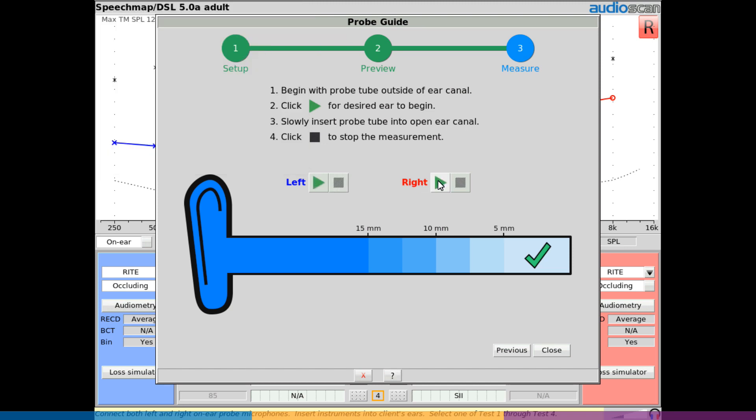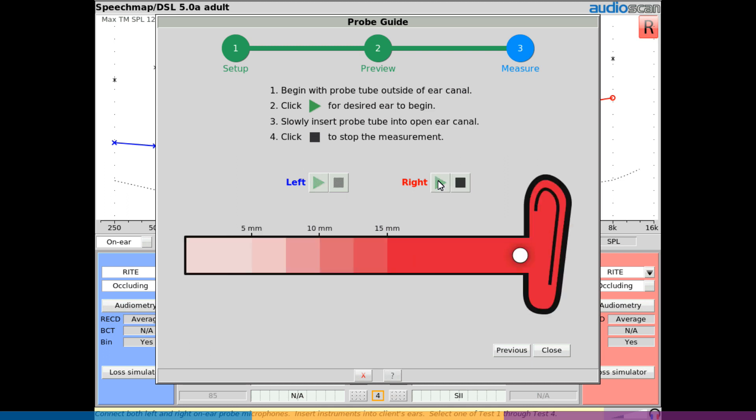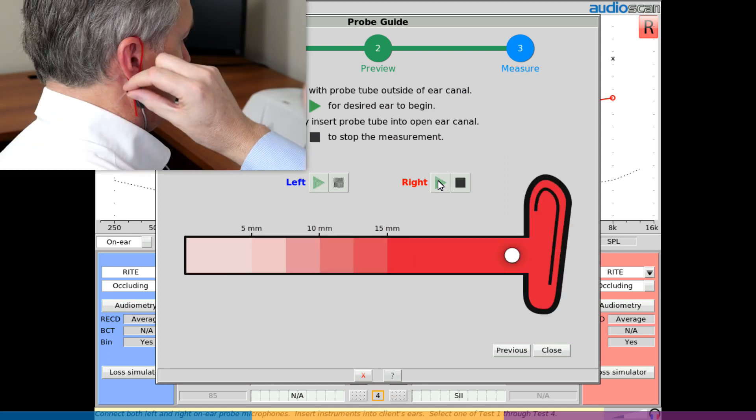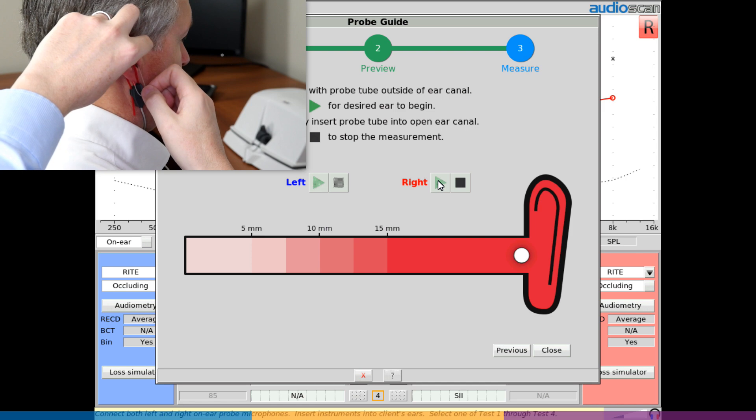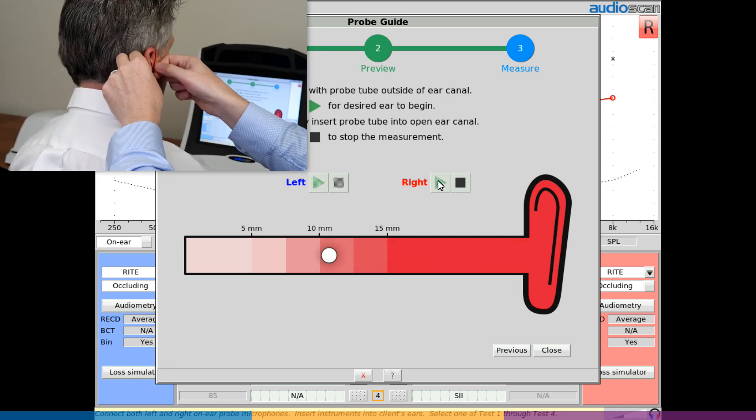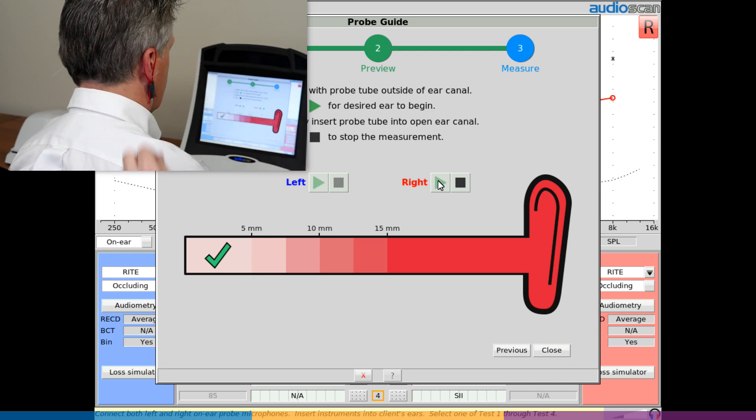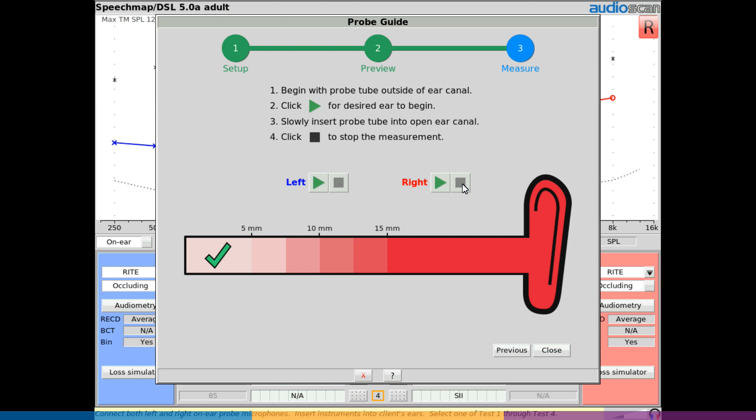Selecting Play for the opposite ear will cause the on-screen orientation to change to match the direction of probe tube insertion. As before, slowly insert the probe tube into the ear canal, passing it around the front of the lanyard. Again, a check mark and chime will indicate successful placement. Click Stop to complete the procedure.